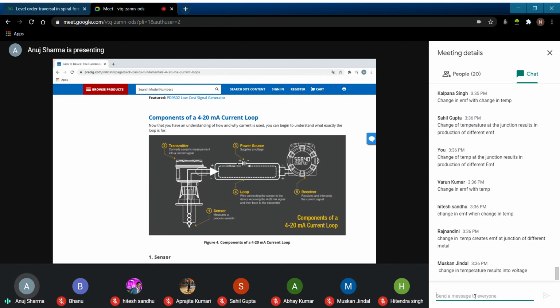Just understand this, that the power supply will try to give the maximum amount of current that it can give. If there is no resistance, it can provide an infinite amount of current. Okay, but the issue is that there is resistance. Now this resistance has been calibrated in such a way that it will range from 4 to 20 milliamps.